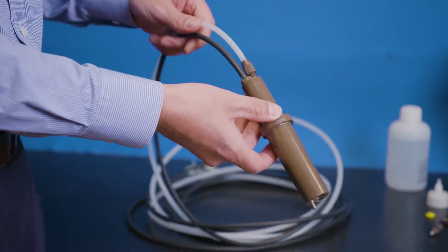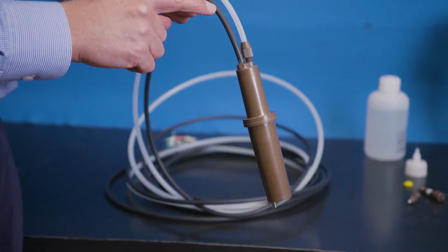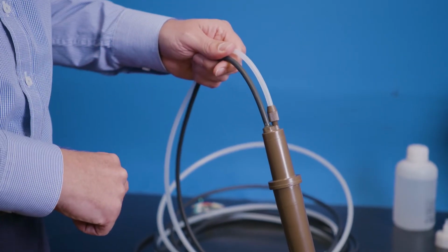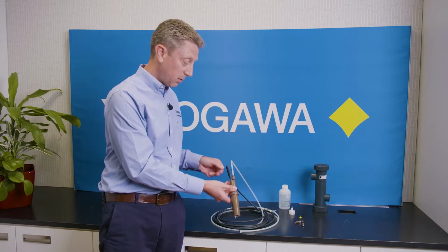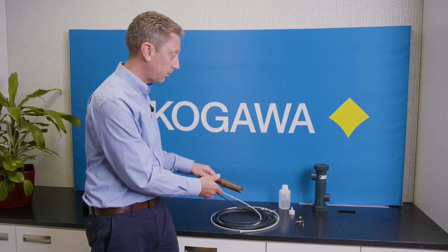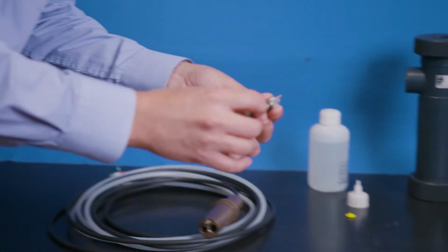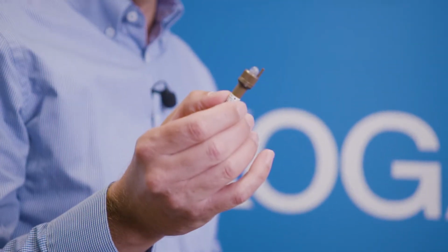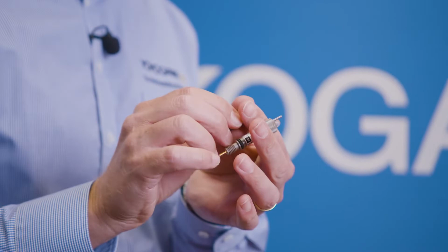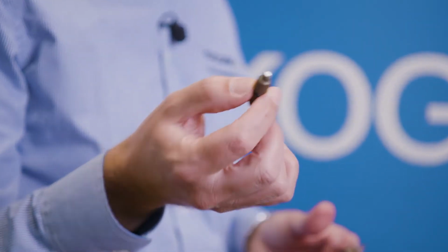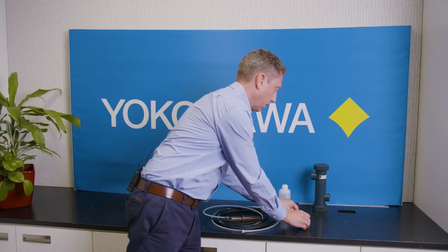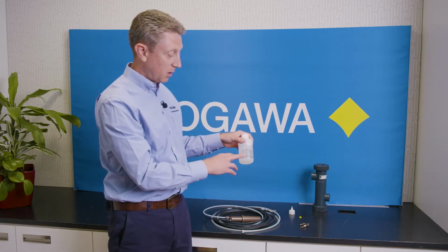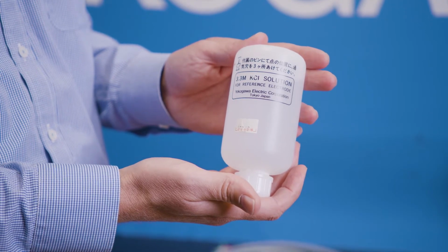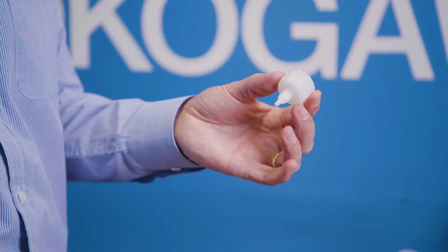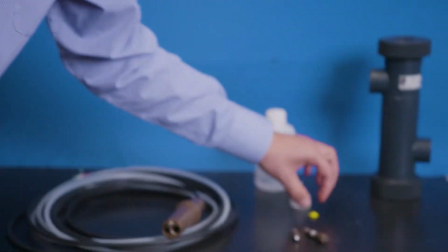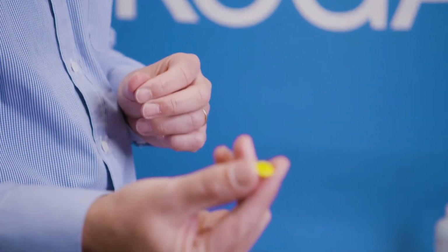So when you receive your new pH sensor, you should receive the main body. This is our PH8 electrode. It should already become assembled with the cable and the KCL hose attached. You should also receive a glass pH electrode as well as a reference junction. Also in the box you'll have one bottle of KCL or potassium chloride solution, a nozzle to connect to that bottle, as well as a little thumbtack to pierce a hole in the bottle.